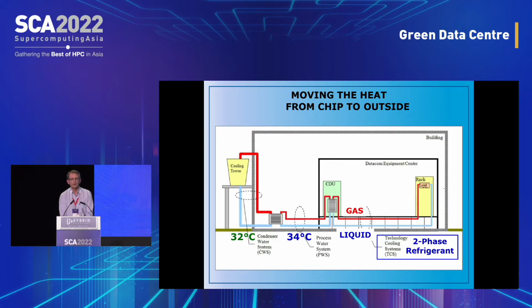If I have a two-phase refrigerant, this is what my improved cycle will look like in terms of moving the heat from the IT equipment all the way outdoors with no compressor, no chiller - free cooling. Obviously, we've got pumps to pump those liquids around, but those use a lot less energy than compressors do. So yes, there's no such thing as free cooling. You still have to pay for some fans, some pumps on the cooling tower, but it's much, much less.